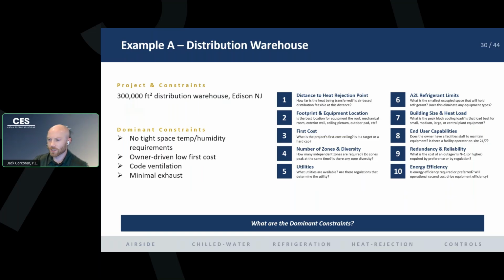And the minimal exhaust. So you're looking at this project. What type of outside air system should we use? You can just use an outside air fan or a makeup air fan in this situation, right? You don't need to temper the air. There's no tight temperature requirement in the space. We can let that air in the warehouse go up to 95 degrees. It's not super important that boxes are maintained at a room temperature that's comfortable for people. You can let that temperature slide a little bit in the summer, and you don't need to spend all the money that you do on an ERV or a DOAS system.